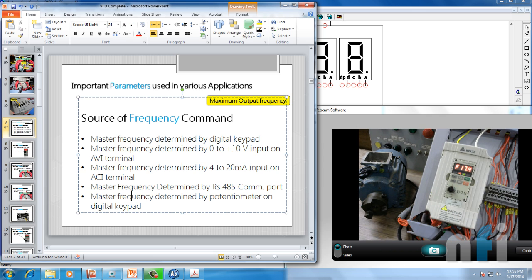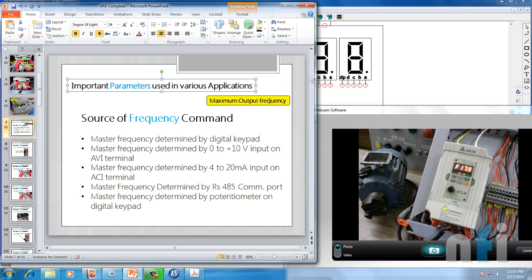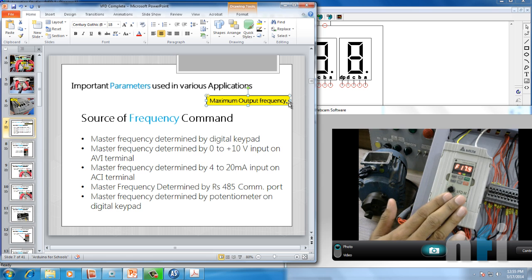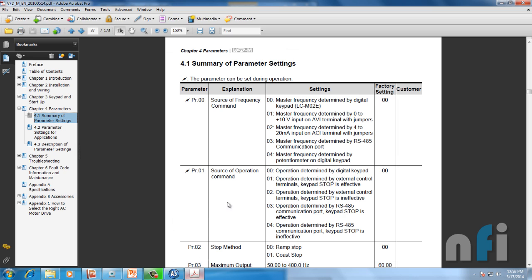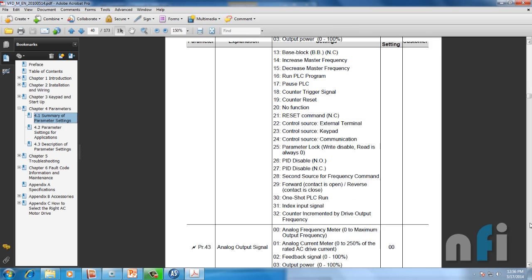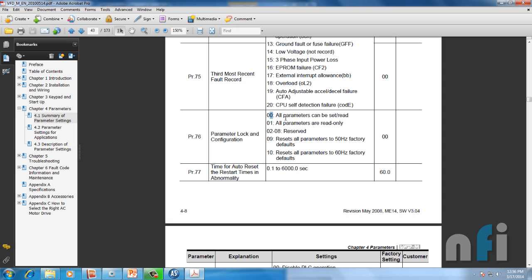Before setting this parameter, we need to mention the maximum output frequency in our drive. Many times you don't know what parameters are already set in your VFD, so the first step a programmer should do before entering parameters is to reset all existing parameters. That way you'll know what parameters you're going to enter and what changes you're going to get. You must always carry the manual of your drive — this is the manual for this drive.